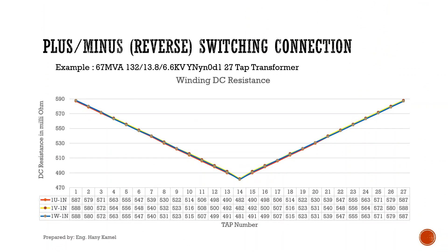For DC winding resistance, we have an example: a 67 MVA transformer, 132 over 13.8 over 6.6 kV, with vector group YNYN0D1 and 27 taps. The DC winding resistance is as shown in the curve. Tap number 1 and tap number 27 have the highest value and both are the same. Tap number 14, the tap changer mechanical center tap, has the lowest value.